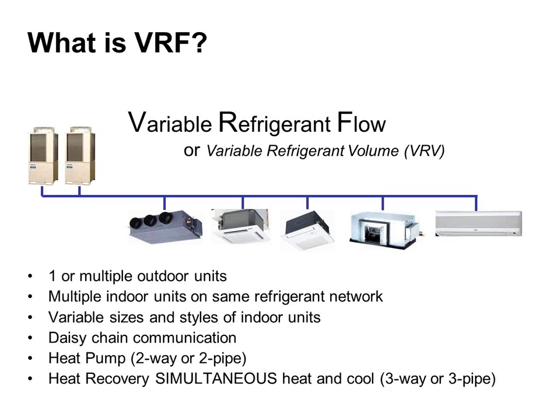But they basically have 3 pipes, so they can provide you hot refrigerant or cold refrigerant, if you will, to each one of your individual units. And any individual unit can be an evaporator or condenser at the same time as another one in the next room is the opposite. And then the outdoor unit trims the difference.